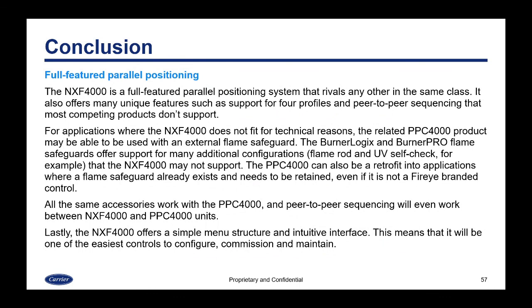So in conclusion, the NXF4000 is a full-featured parallel positioning system that will rival any other in the same class. It also offers many unique features, such as support for 4 profiles and peer-to-peer sequencing, that most competing parallel positioning systems don't support. For applications where the NXF4000 does not fit for technical reasons, we have the related PPC4000 product, and that may be able to be used with an external flame safeguard. The Burner Logix and Burner Pro flame safeguards offer support for many additional configurations, such as flame rod and UV self-check, that the NXF4000 may not support.